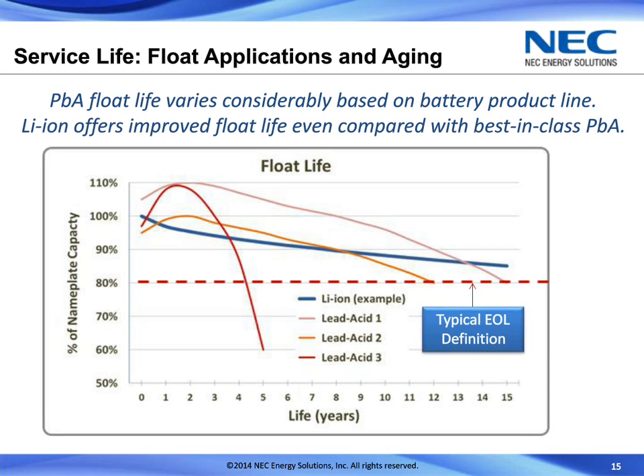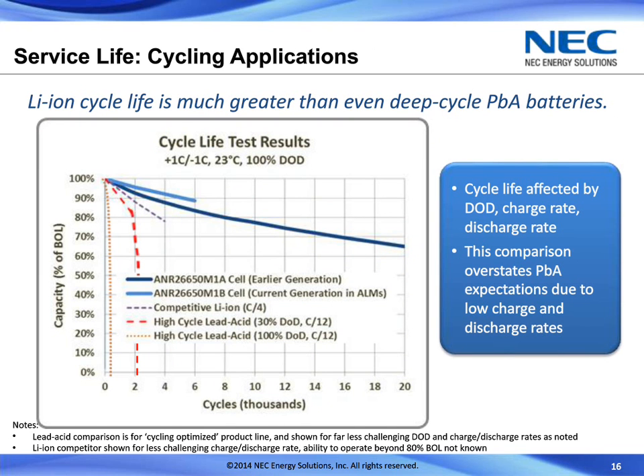The other aspect of service life is in cycling applications. And this is the area where the lithium-ion, as a general technology, has really shined compared to lead acid. This is the reason why it's in our cell phones. This is the reason why it's in our laptops. This chart is an illustration of actual test results from the cell technology that we happen to use in our ALM lithium-ion product line. In fact, it's the same technology used in our grid storage systems. And this is demonstrating a cycle life, even at a relatively high charge and discharge rate, that can exceed 8,000 cycles to 80% of the beginning of life capacity. So when the capacity drops to 80% of its beginning of life, we're at 8,000 cycles.